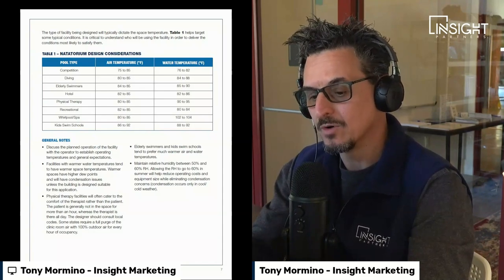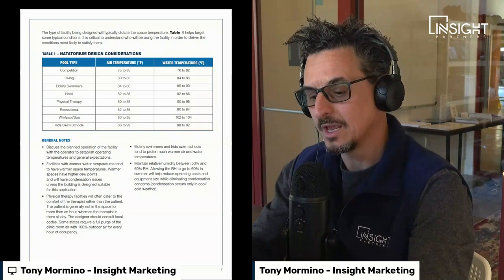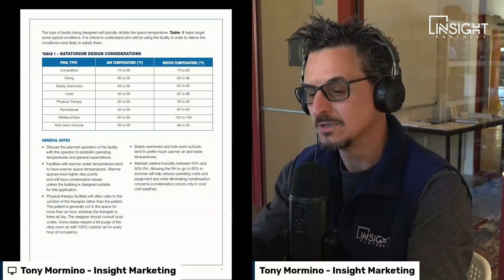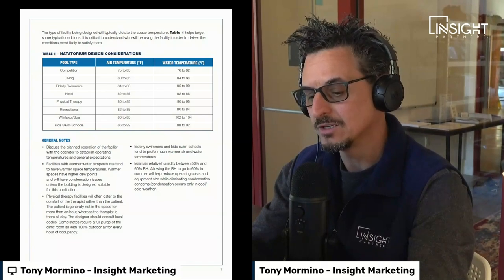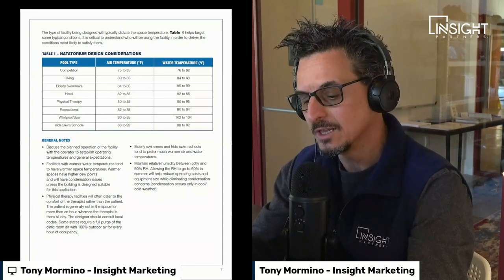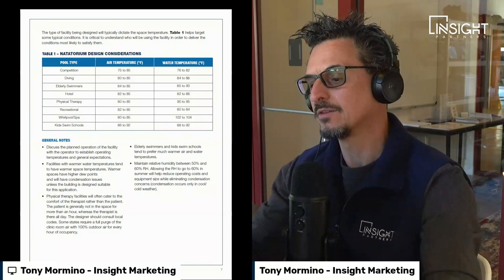Some general notes: first, discuss the planned operation of the facility with the operator to establish operating temperatures and general expectations. Second, facilities with warmer water temperatures tend to have warmer space temperatures — warmer spaces have higher dew points and will have condensation issues unless the building is designed suitably. Third, physical therapy facilities often cater to the comfort of the therapist rather than the patient, since the patient is generally not in the space for more than an hour whereas the therapist is there all day. Designers should also consult local codes — some states require a full purge with 100% outdoor air for every hour of occupancy.